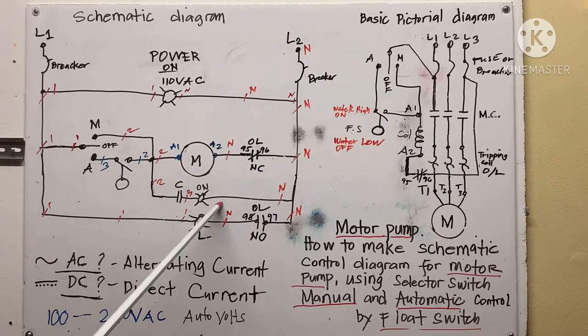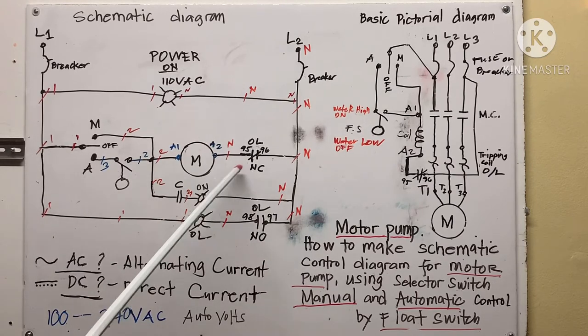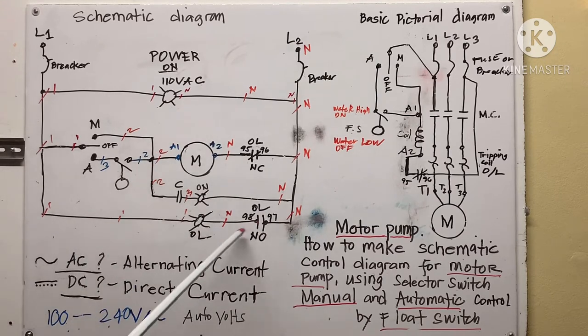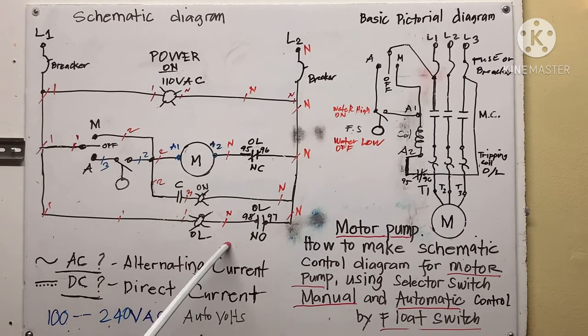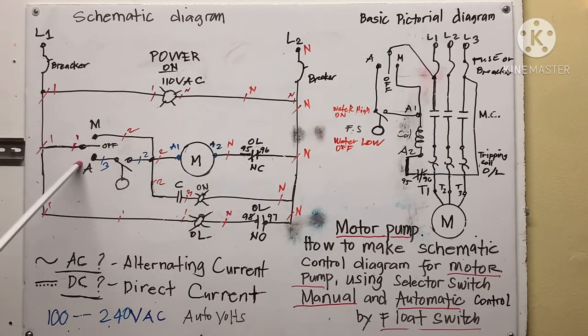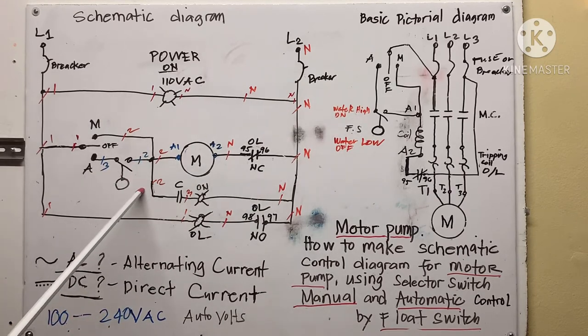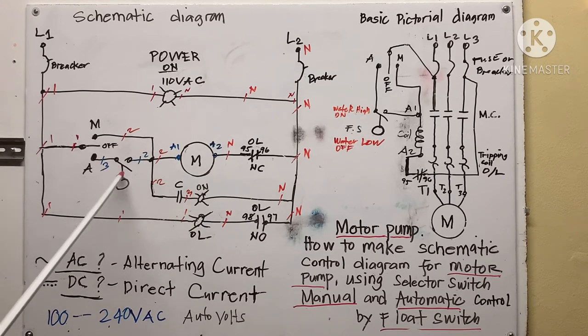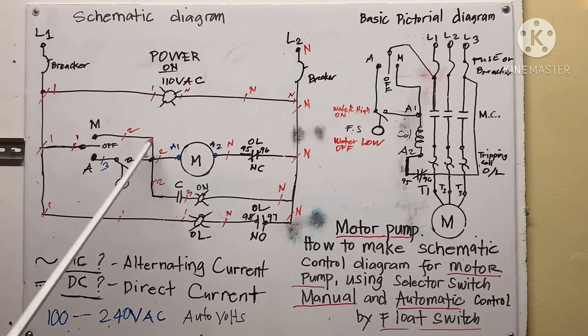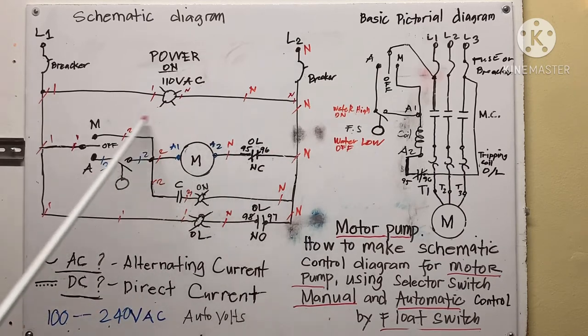When the motor is overloaded, this contact opens, and the overload indicating light comes on. When you put it in automatic, it's controlled by the float switch. When the water level closes the float switch contact, it goes automatic — that's why I made this schematic diagram.